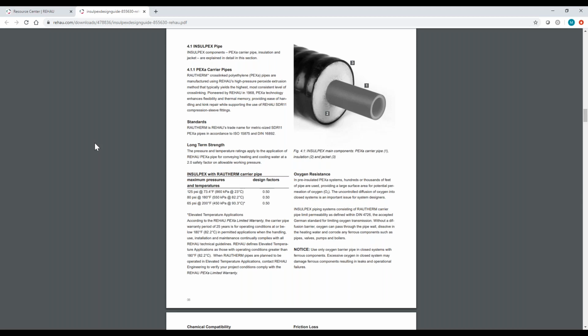One of the big advantages with hydronics is that a lot of the projects we're working on with radiant heating and radiant cooling stay really low on the temperature range, so we don't need 180 degree Fahrenheit, also because we're not losing so much temperature. If you needed 140 degree Fahrenheit water at the end of a 500-foot trench, you might have to supply something a lot warmer with a different type of product.